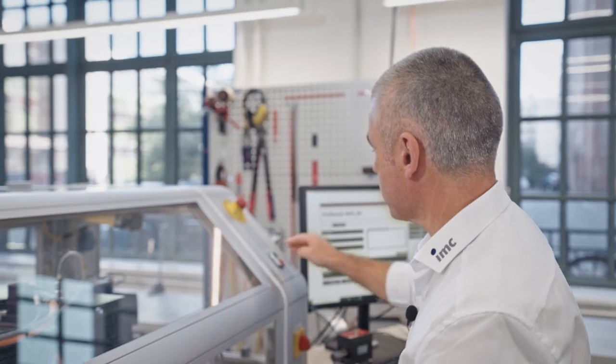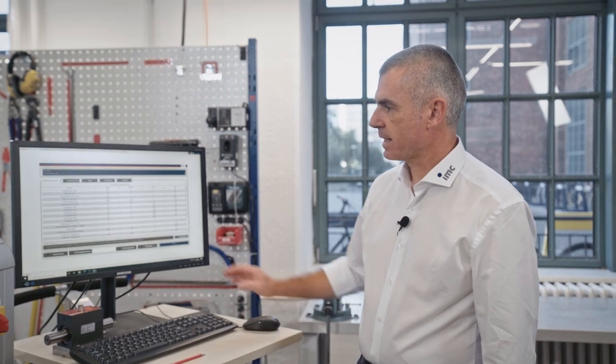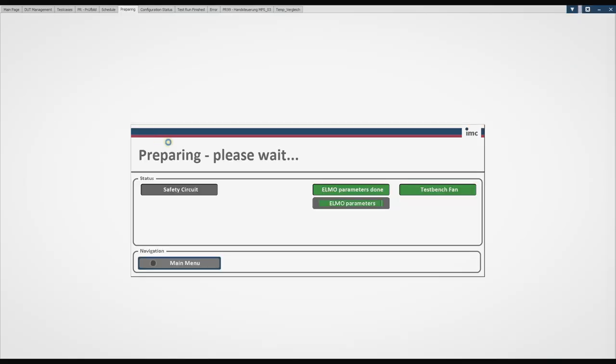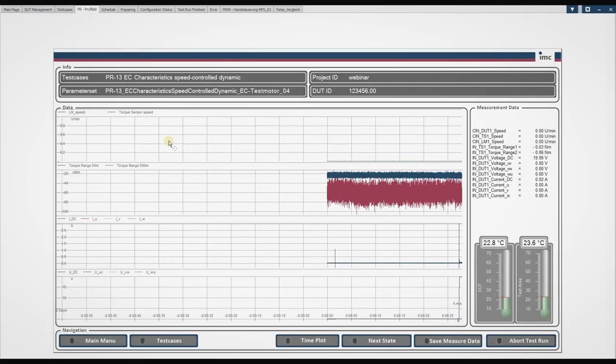After preparation of the test motor, we close the safety lid and the safety circuit and start to prepare the test — entering metadata like the project ID or the serial number of the test motor. We select the proper parameters for this motor, which include voltage, current, speed, torque, and so on. We go to the test selection and press start. During preparation, the configuration data are loaded back to the automation system, the safety circuit is checked, and the controller data are downloaded to the system.